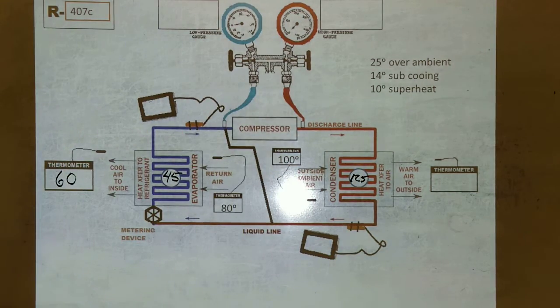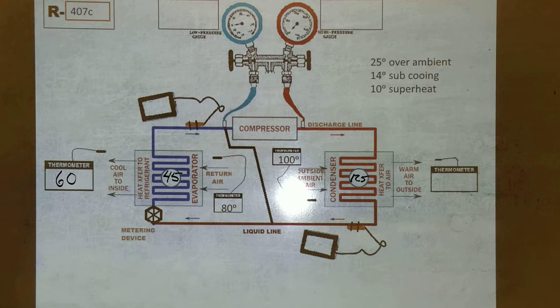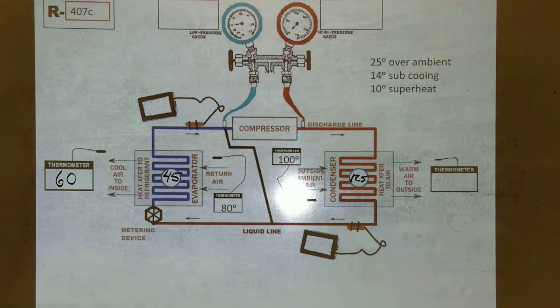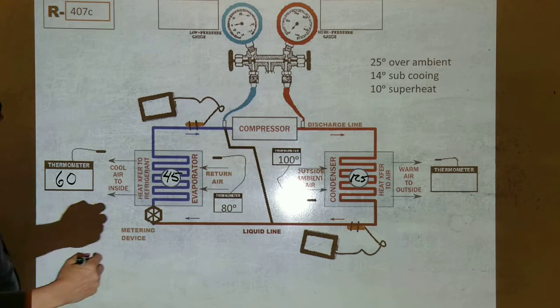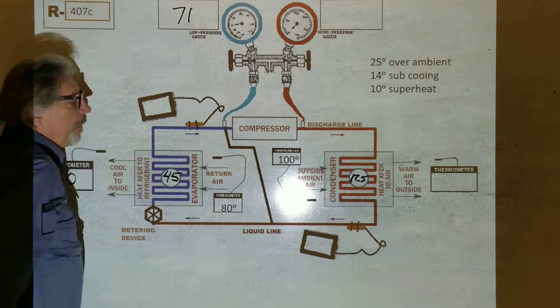Okay, so as far as our pressures are concerned, what pressure should we be reading on our gauges under this condition? Low side pressure is 70 PSIG. 70.6. I don't think so, Tim. I got 118 for 407C? Yeah, I think so. 70.6 or 70.7. 71, okay, we'll round up.